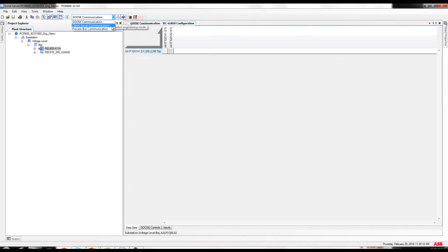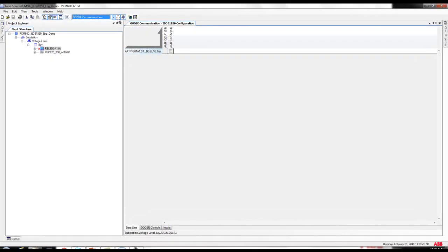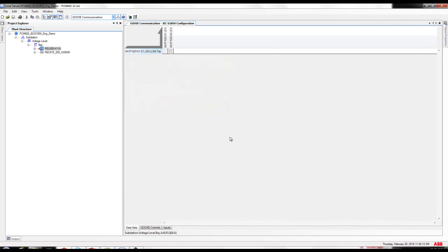By default, the IEC 61850 configuration shows you the GOOSE communication. If you click here, we have the client-server communication and process bus communication. At the moment, we are going to use only the GOOSE communication and client-server communication. By default, the engineering mode is disabled, so you might have to enable it by clicking on the tool. The first step is to create the datasets on the IEC 61850 tool, then the GOOSE control block, and the same for the IEC 61850 REC670.